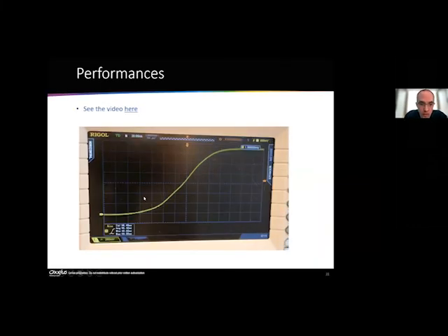Okay. So this was to show you how you could be measuring the actual rise time of the L1C. Such a short rise time is difficult to achieve using a standard DPSS laser, especially a laser with a single longitudinal mode.